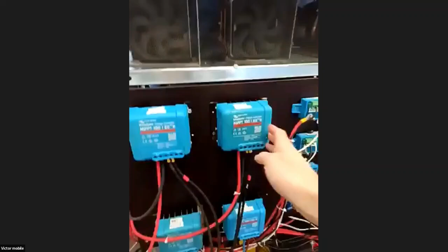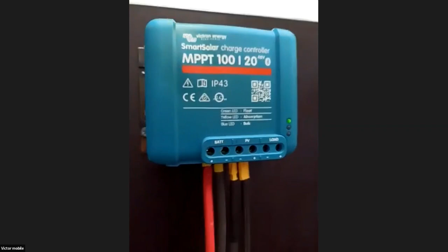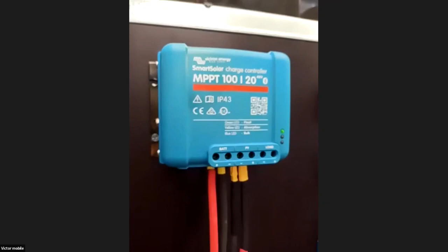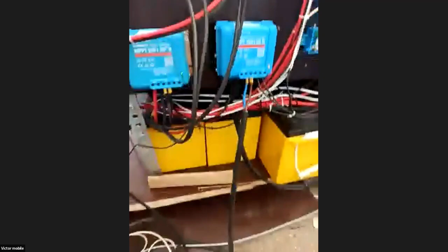Let's go inside and see how we connect the cooling units to the system. We just saw the PV panels, which are connected here to the charge controllers - here's the connection for PV and then for the batteries. These are maximum power point charge controllers that make the system run at maximum power. Here are the batteries we're using, and the charge controllers connect to the battery protect systems, which allow the cooling units to consume energy only when the voltage is high enough.